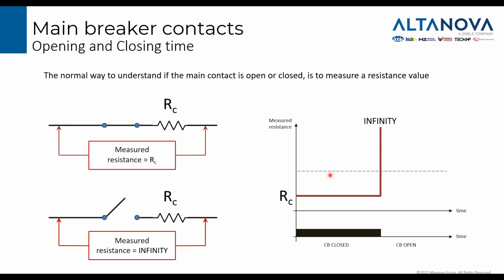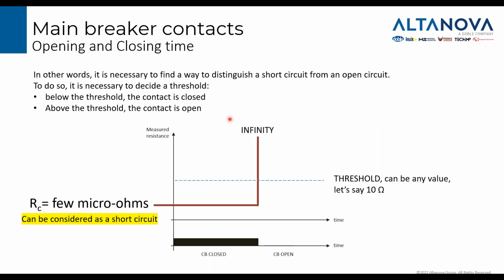But when we use an electronic device, we have to put a threshold somewhere in order to understand what low value and high value of resistance mean. In this representation, you see a dashed line that represents exactly this threshold. Typically, this threshold with standard devices is around 10 ohm. It's a reasonable value because when the circuit breaker is closed, the value is in the range of a few micro ohms, so it is a short circuit. Whatever is higher than 10 ohm is clearly correlated to an open position.